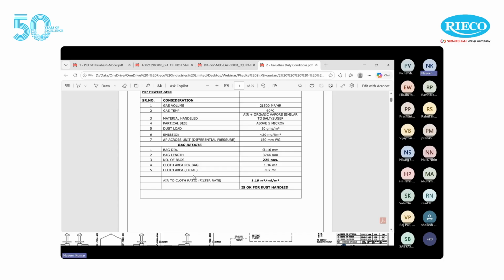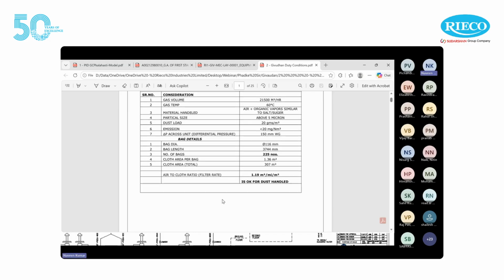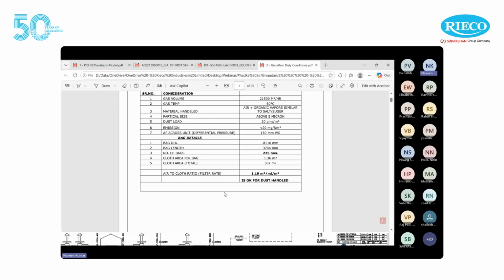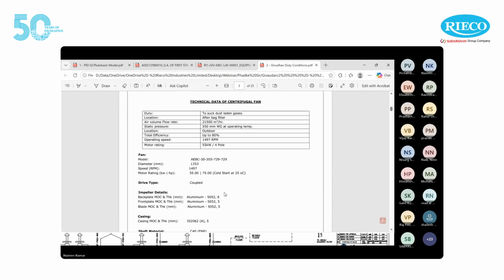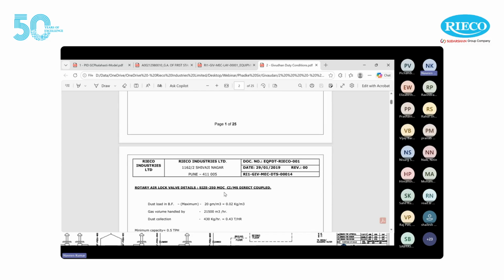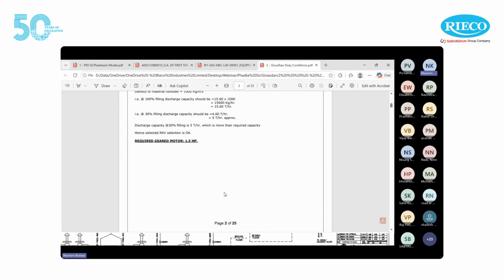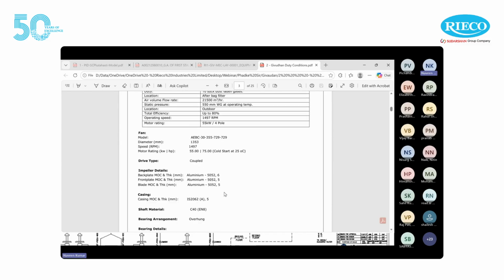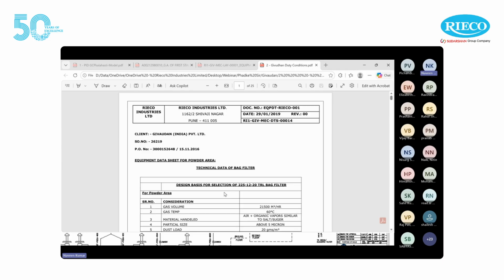And then these are the specifications for the bag filter, where we are using the bag diameter of 116 millimeters and a bag length of 3.7 meters. We have a total cloth area of 307 meters square, resulting in an air to cloth ratio of 1.19 meter cube per meter square per minute. Yeah, these are the specifications for the fan.